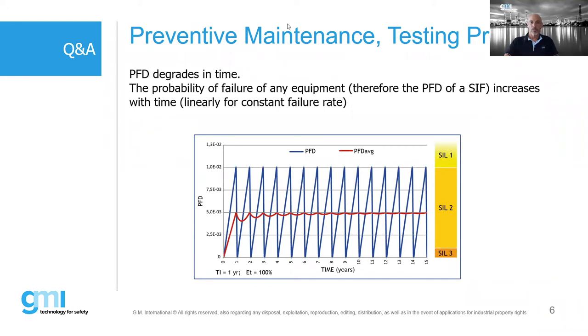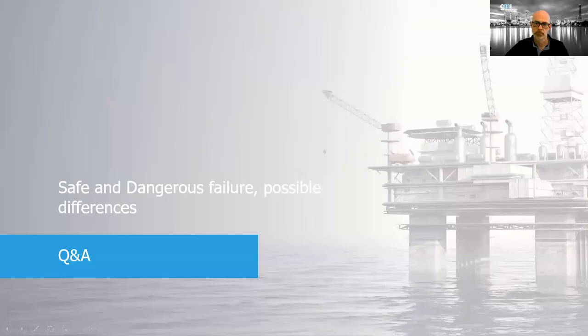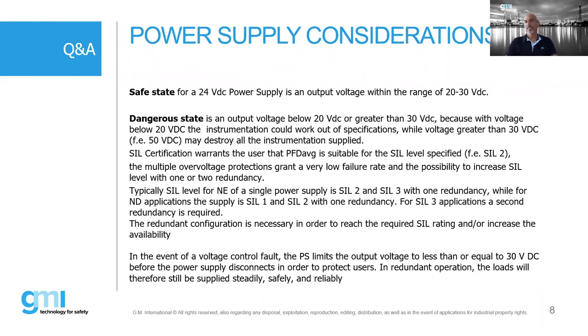Okay, let's continue with the presentation. Safe and dangerous failures, possible differences. So we already said that the safe state for the power supply is a voltage in the range 20 to 30. That is the safe state. Dangerous state is below 20 or over 30. Below 20 is a problem for the instrumentation, because the instrumentation could work out of specification. But if you go higher than 30, it is also a problem because it can destroy the instrumentation. So that is maybe the most important thing.